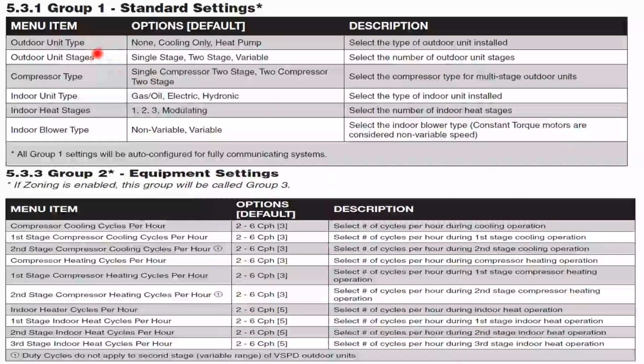Group 1, standard settings. Now, if it's communicating, all of this is going to be picked up. You're going to have the air handler, but we have to tell it if it's electric or gas and oil. So if you're dual fuel, you're going to do gas. If you're heat strip, you're going to do electric. And if you're doing the hydronic heat strips, you're going to have hydronic. And then we are variable speed. So we're always going to select variable. So that's something that you're always going to have to select.